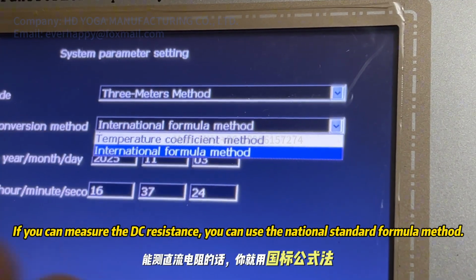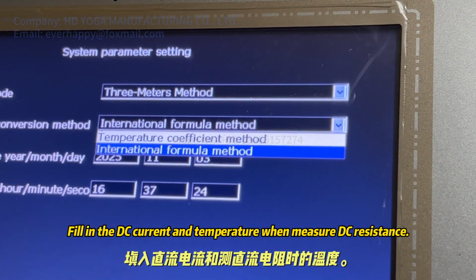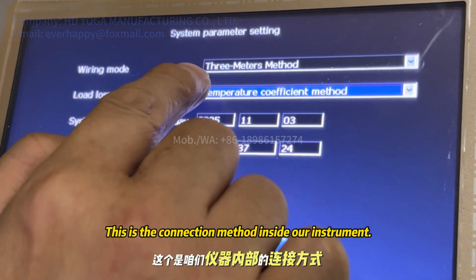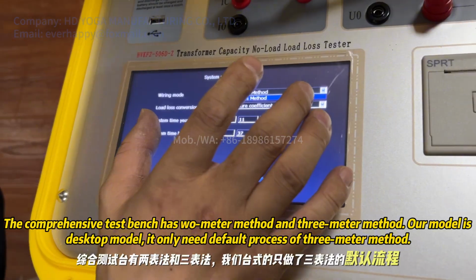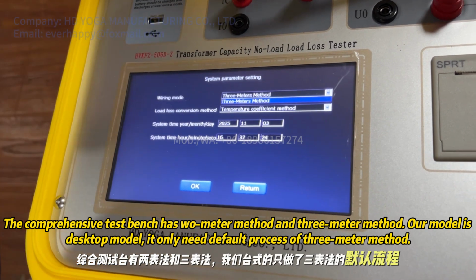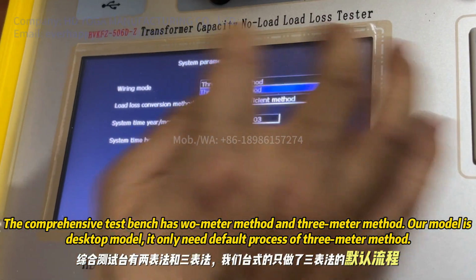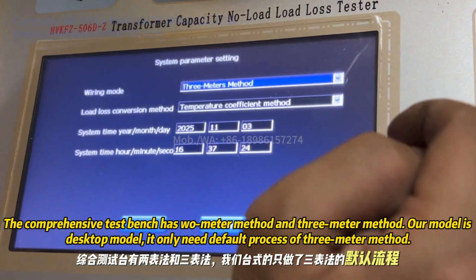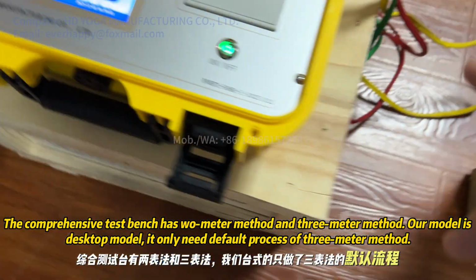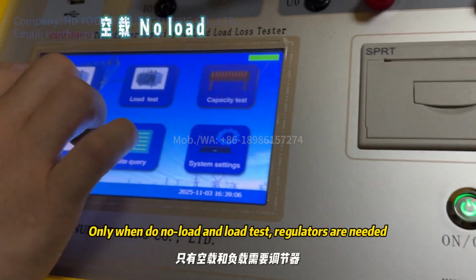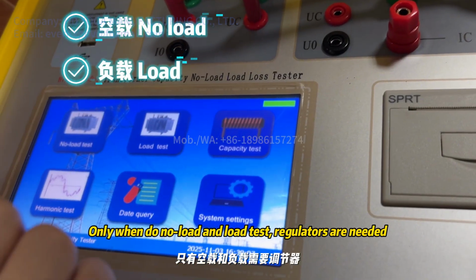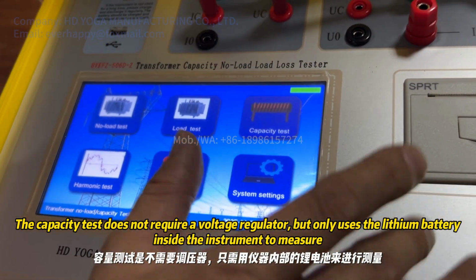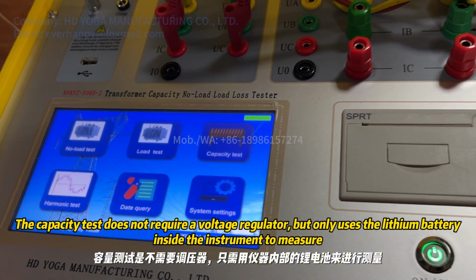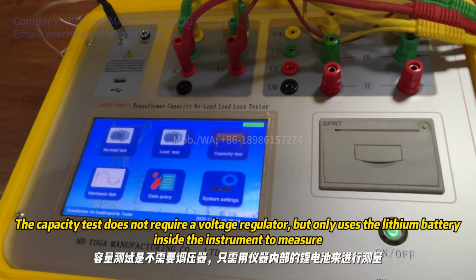If you can measure the DC resistance, you can use the National Standard Formula Method. Fill in the DC current and temperature when measuring DC resistance. This is the connection method inside our instrument. The comprehensive test bench has the two-meter method and the three-meter method. Our model is desktop model. It only needs the default process of the three-meter method. Only when doing no load and load tests, regulators are needed. The capacity test does not require a voltage regulator, but only uses the lithium battery inside the instrument to measure.